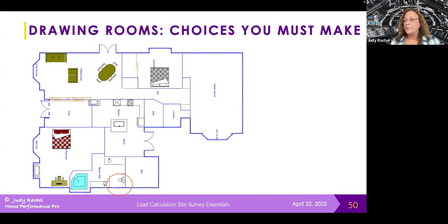There are also sometimes little rooms that won't have enough load for me to draw them as a separate room. So I put things in so that you could visualize what I was seeing in the field, but I didn't actually draw this little water closet as a separate room. I included it in the entire master bathroom. Partly that's from experience of having drawn in these little water closets and seeing that the load is not enough that I would want to directly condition it, and I know that when I mix a room well, this area is going to be conditioned as well. So some of it's from experience.